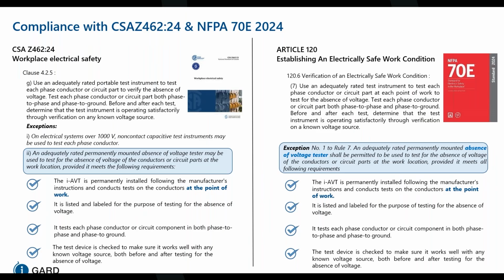CSA Z462, the 2024 revision, and NFPA 70E 2024 now allow a permanently mounted absence of voltage tester to confirm the equipment is de-energized, provided it meets strict requirements. AVTs must test at the point of work, be listed for absence of voltage testing, check all the phases, and verify their own operation before and after testing. This makes AVTs a faster, safer, and fully compliant alternative to handheld testers.